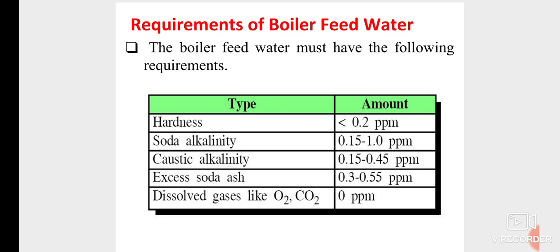The boiler feed water must have the following requirements: hardness should be less than 0.2 ppm or ideally zero. Soda alkalinity should be in the range of 0.15 to 1 ppm — above this range it will affect the boiler. Caustic alkalinity range is 0.15 to 0.45 ppm. Ppm means parts per million — one milligram of solute dissolved in one liter of solvent. Excess soda ash: 0.3 to 0.55 ppm. Dissolved gases like oxygen and carbon dioxide: 0 ppm. These are the basic requirements of the boiler feed water.